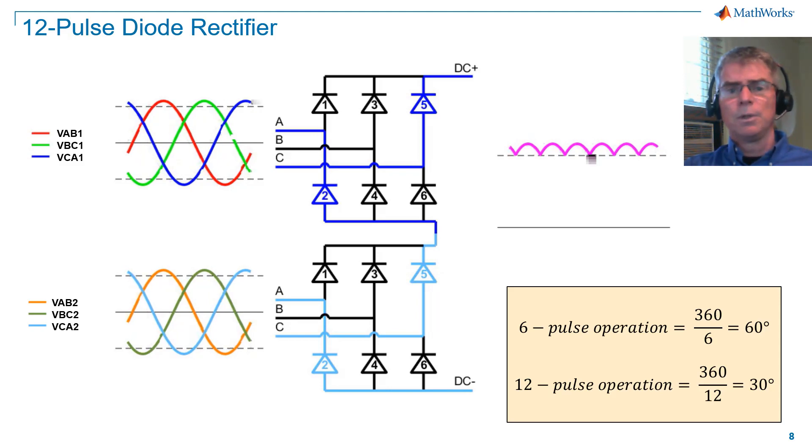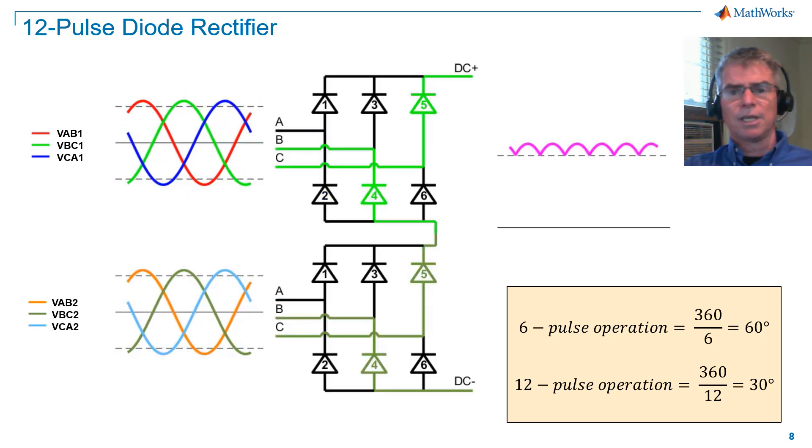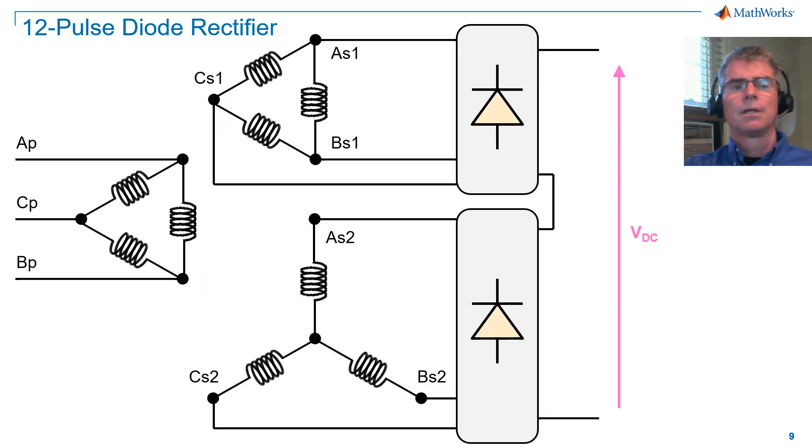To do this, we phase shift the lower secondary relative to the upper secondary. Here we have a 30-degree phase shift between the upper and lower secondaries. I've changed the lower secondary to a star configuration and left the upper secondary as a delta D1. Let's see what happens now.